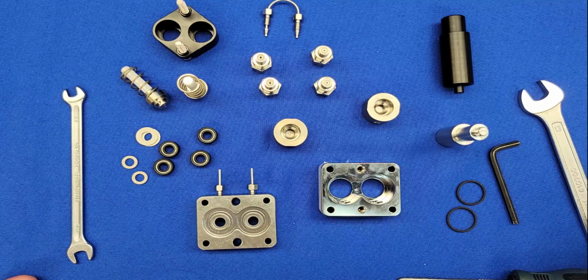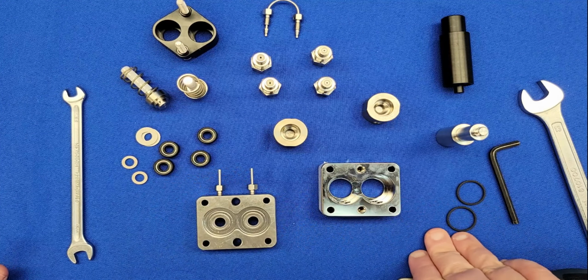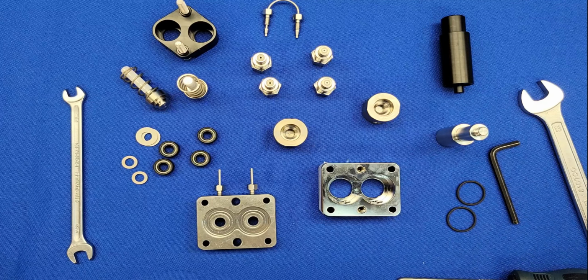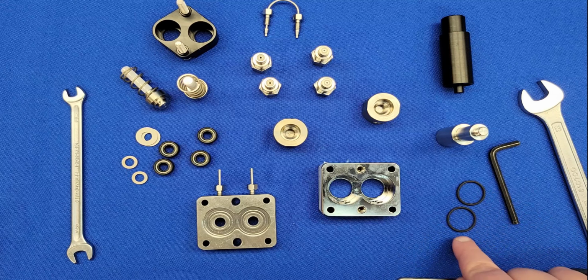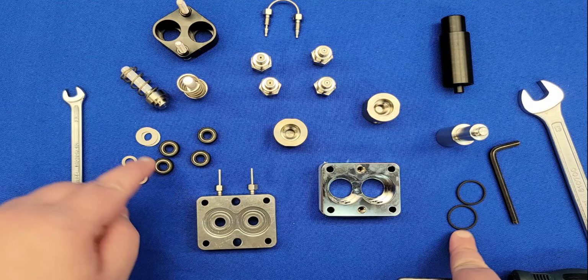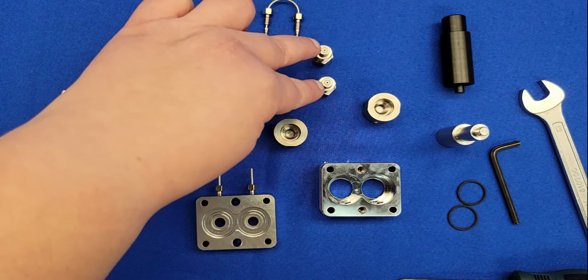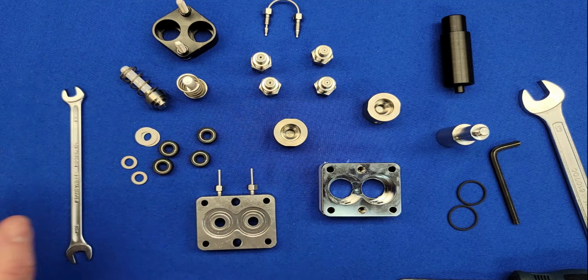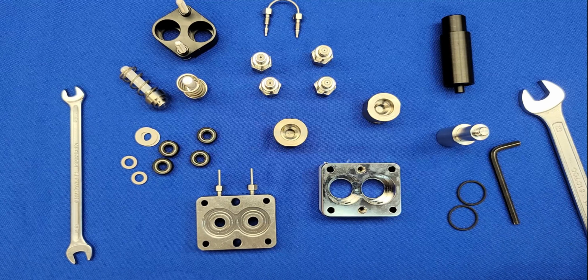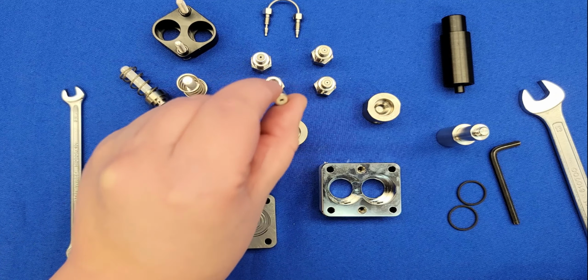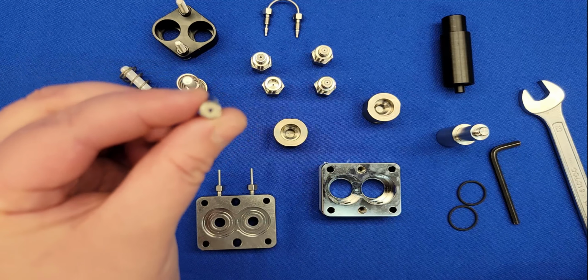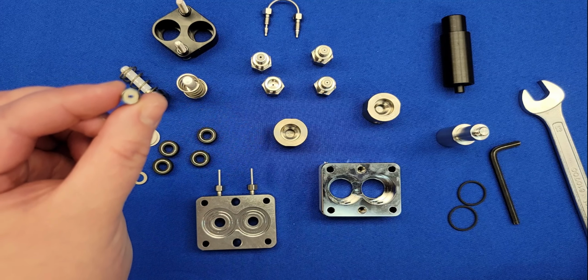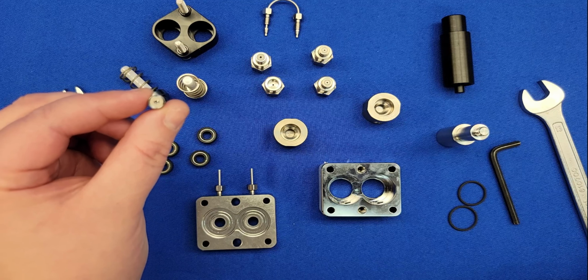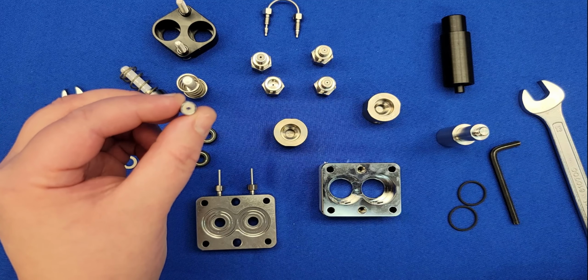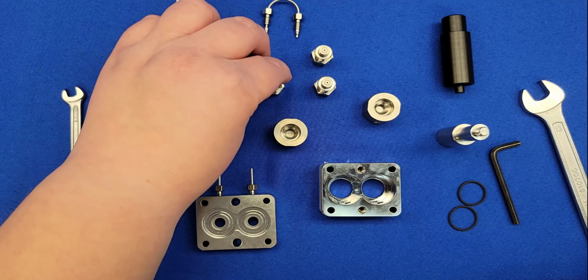Okay, so usually you would have your replacement parts. For the sake of the video, I'm just going to reuse the same ones, but technically you would have to replace your O-rings, your seals, your 2 pistons, and your 2 check valves. The dummies can be reused, that's not an issue. The only time we would have to change them is if they are plugged, and you would be able to see it because this hole is big enough that we can see light through it. So if you see that there's a particle blocking the light, then that's your key to change those. Otherwise you can just reuse the same.